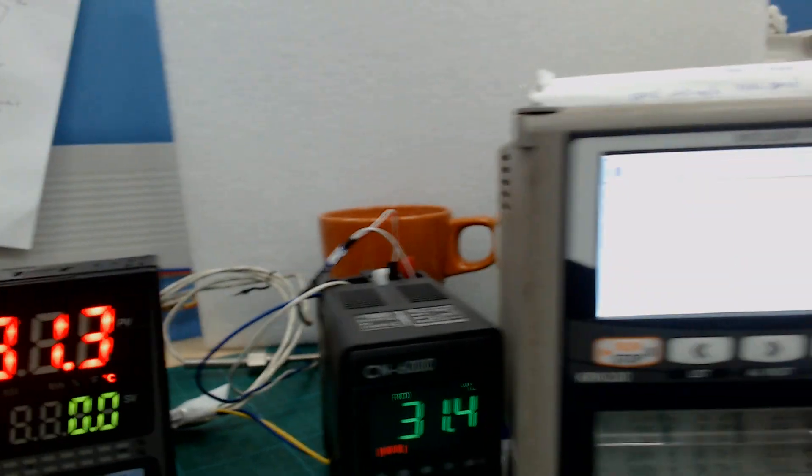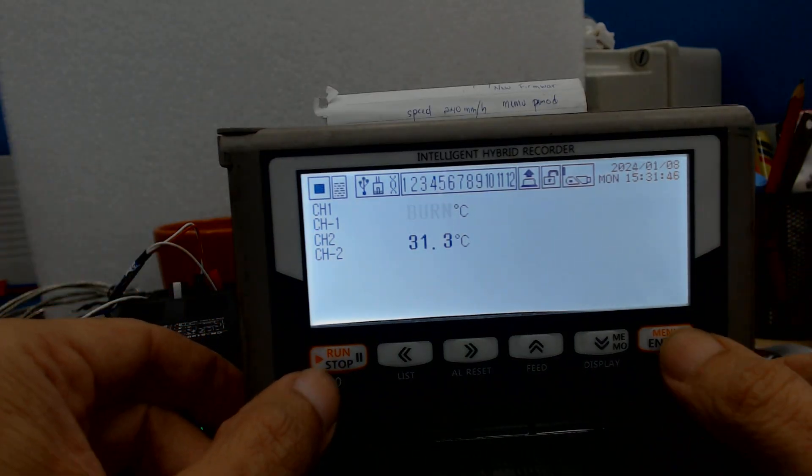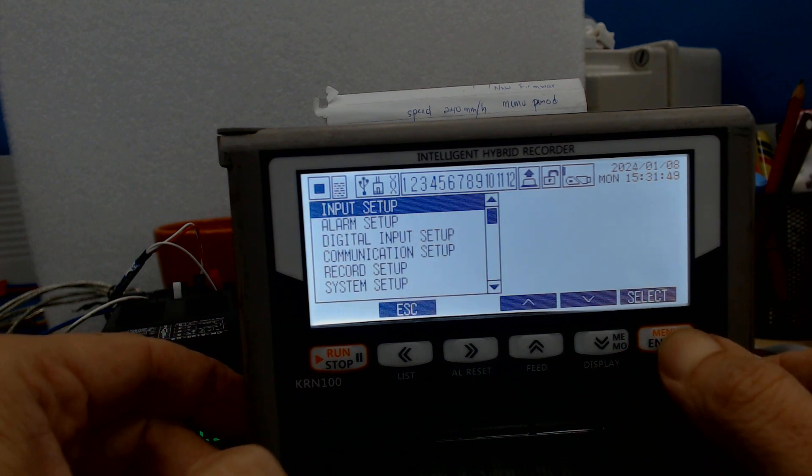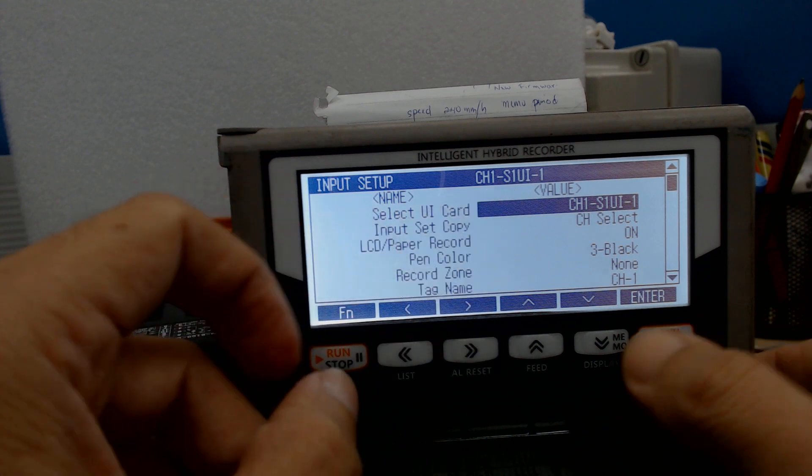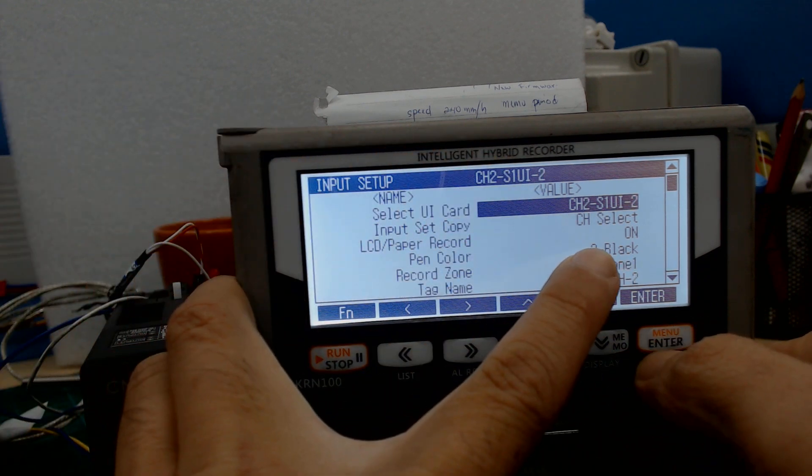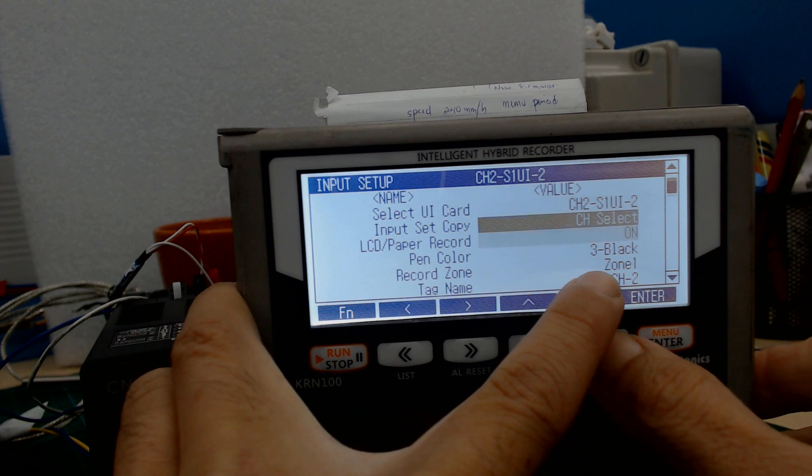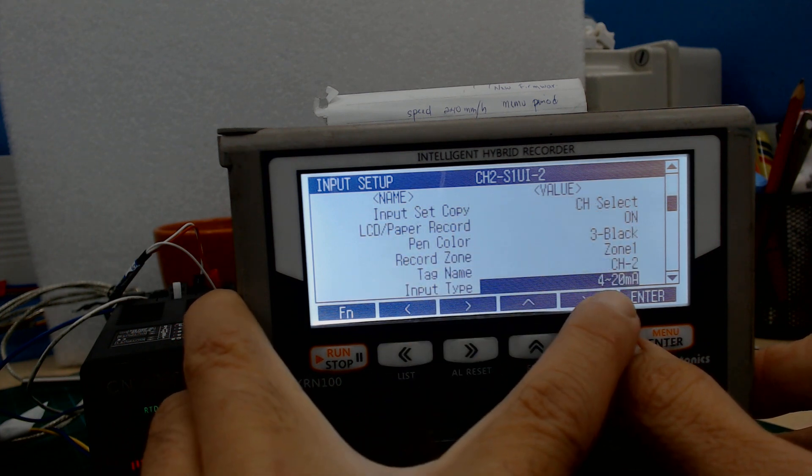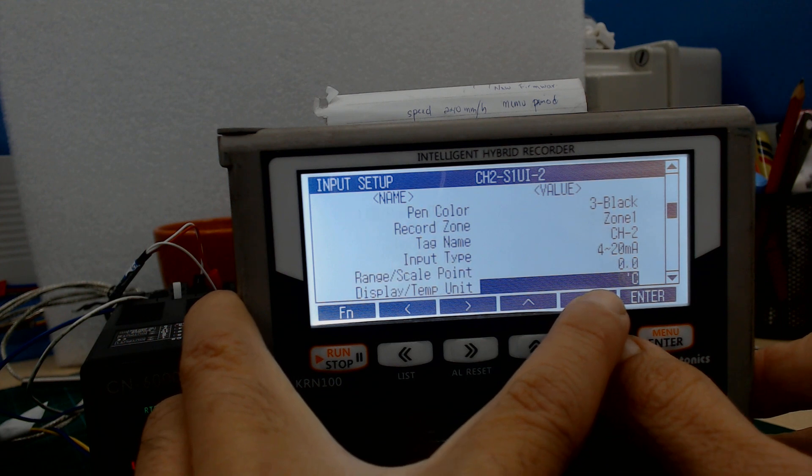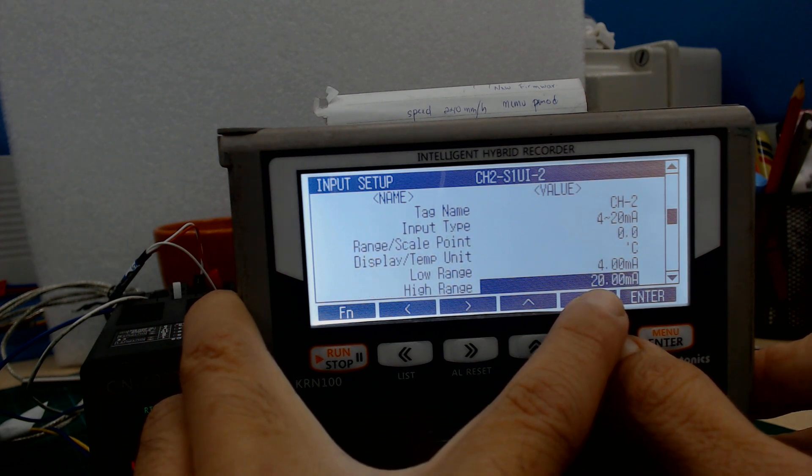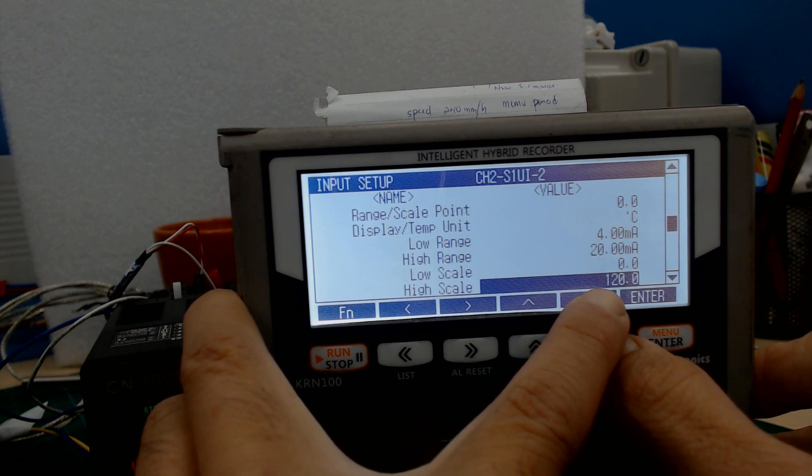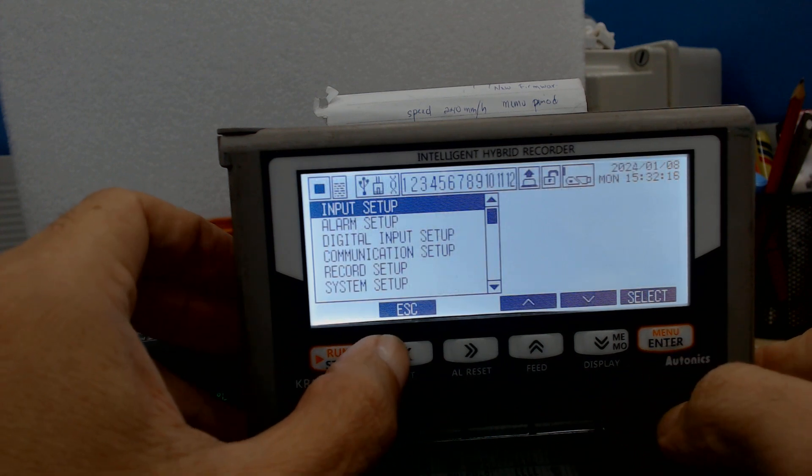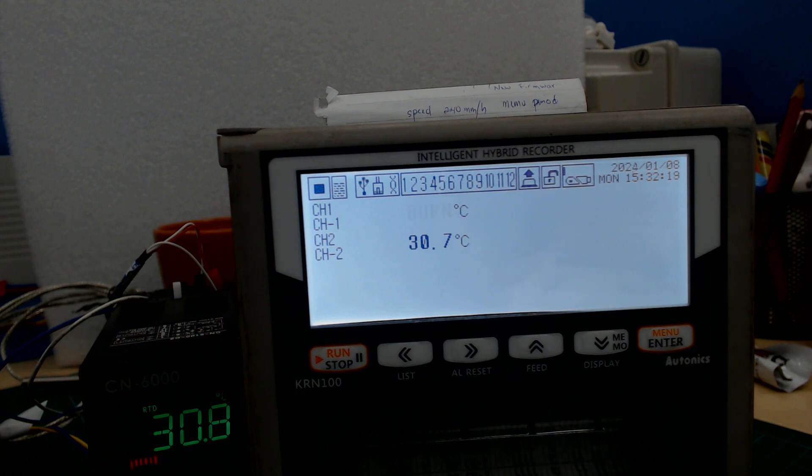We go to the recorder. Press menu, input setup. Now I use channel 2 for the signal. Channel 2 input is start 4 to 20mA. Scale is zero, temperature unit is Celsius. Low scale is zero, high scale is 120. No need resistor or whatever, just wiring.